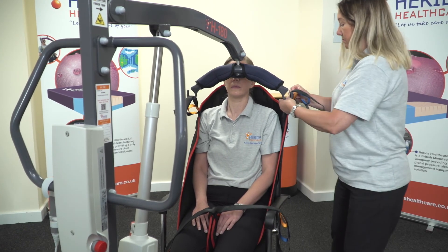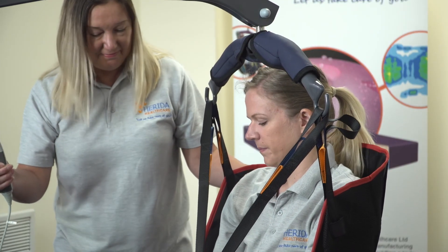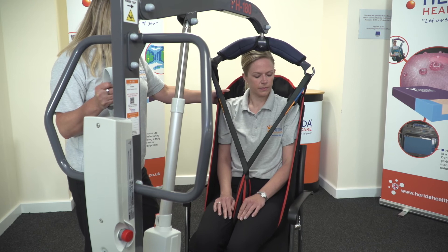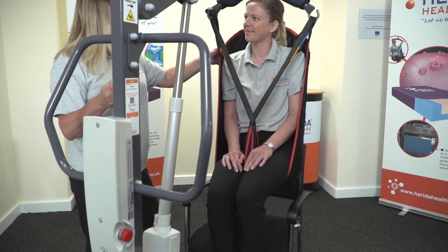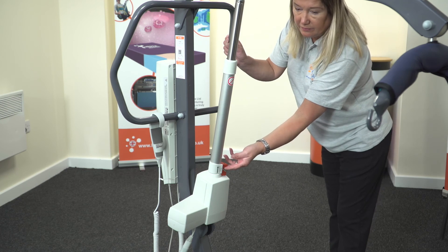Now attach to the 4 or 2 point spreader bar, making sure that it is not too close to the patient's face. You can now safely lift your patient by raising the boom. Do not raise the boom any higher than required. Move the patient, chair, commode or toilet depending on application and then lower the boom by the handset control. Always ensure that the patient will be placed correctly and safely whilst communicating throughout to the person in your care. If for any reason the hoist actuator does not work, which may be as simple as a flat battery, there is an emergency manual lowering mechanism which is triggered by pushing the red lever, located at the bottom of the actuator.